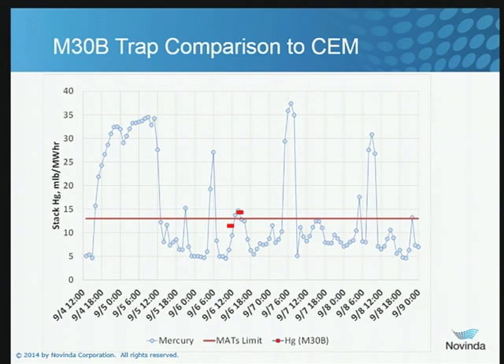Here's that same set of data with two Method 30B traps superimposed. Here's the CEM data, here are trap 1 and trap 2 — and you can see they match up quite well with the CEMS data. We were very pleased with the quality of the correlation here.